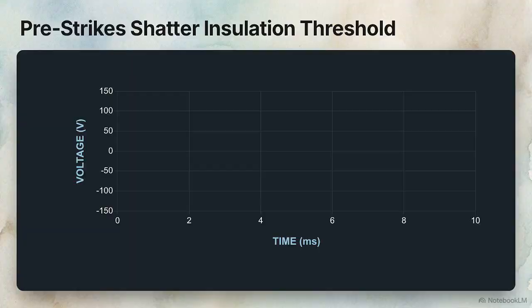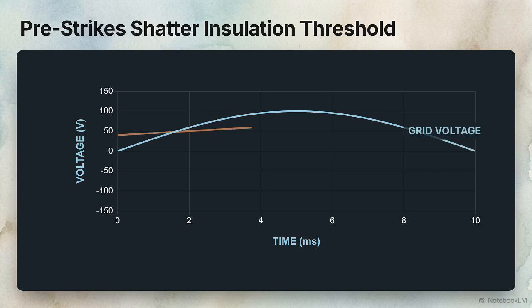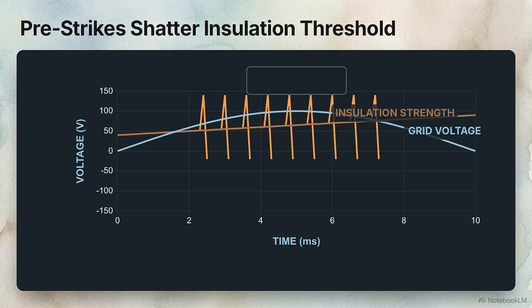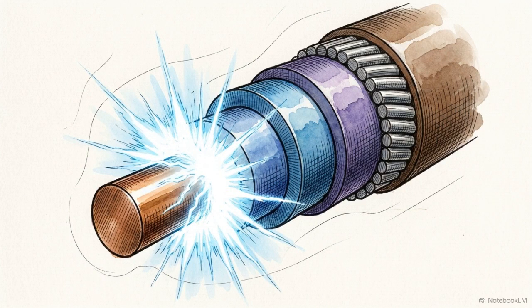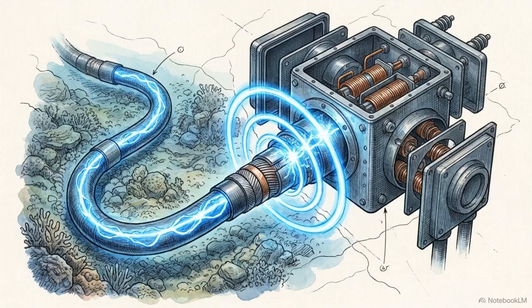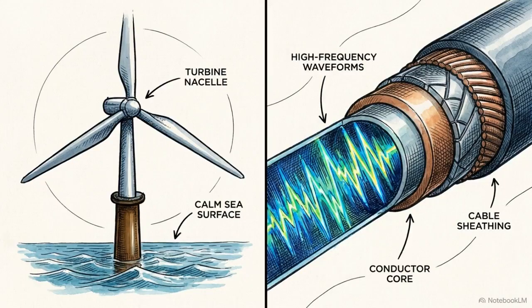current. This graph tracks a split-second race. The rising wave is grid voltage, trying to jump the gap. The straight line is the vacuum's growing insulating strength. In capacitive networks, voltage repeatedly wins. It punches through the vacuum, causing rapid-fire arcs called pre-strikes. Each of those microscopic arcs launches an incredibly steep, violent voltage spike down the submarine cables, where it reflects and amplifies against the ends of the line.